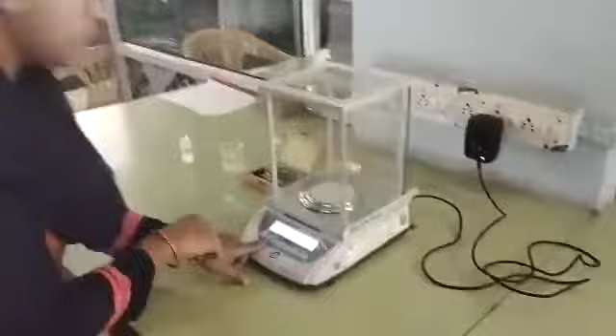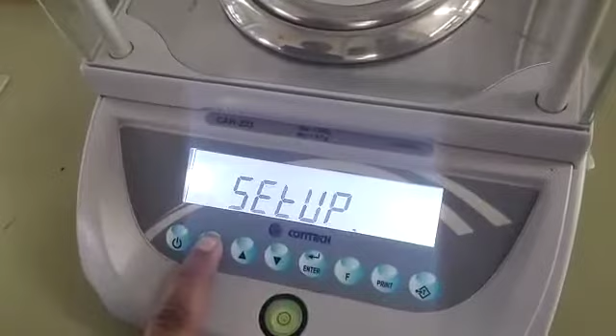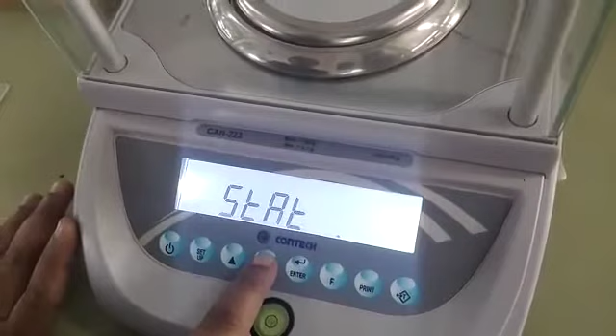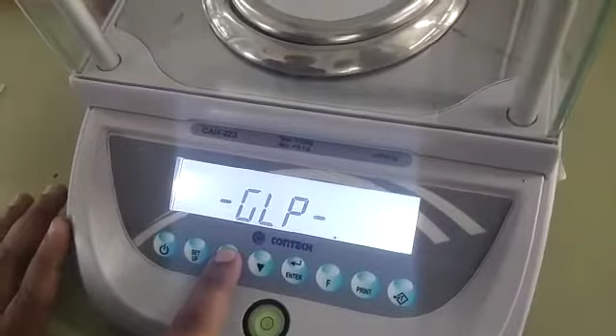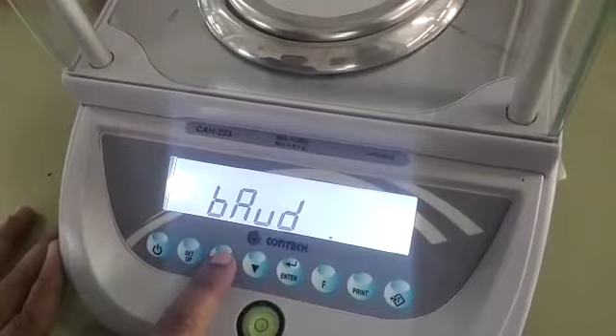So first we see the setup function. For the setup function, we first switch on the instrument by plugging the adapter into the socket and keeping the setup button pressed until the display shows setup. You can see the display shows setup. We can use the up and down keys to change the parameter. I have already set some parameters such as serial number, date, auto zero, storage of memory in weight. I will show you how to set the storage of memory in weight.